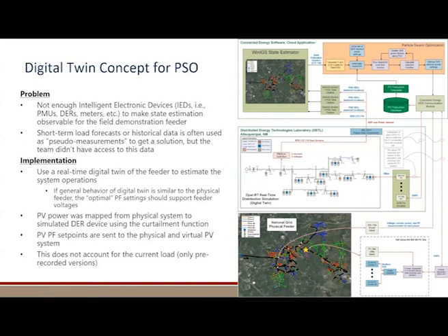Of course, there are a lot of challenges associated with that. We're not really capturing live load data. We do know the irradiance at that PV site based on measurements, and so we can use a curtailment function to send the curtailment to the simulated inverters. And so we're getting pretty close in terms of active power contribution from each of the DER devices in the simulation.